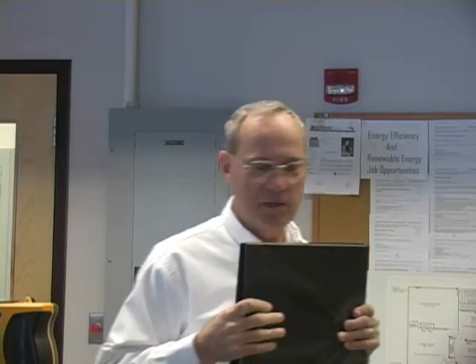It's been in this room and it's at a certain temperature. It doesn't matter if I point it at the window, if I point it at you, if I point it at the furnace, it's a certain temperature, right? So you could grab this thing. If you took an infrared image of this thing right now and it said it was minus 20 degrees, would you believe it? If it said it was 190 degrees, would you believe it? I'm holding on to it. I'll tell you. But a highly reflective surface, and I'll show you that, can tell you exactly that. It's fooling you dramatically. This is what this is doing.